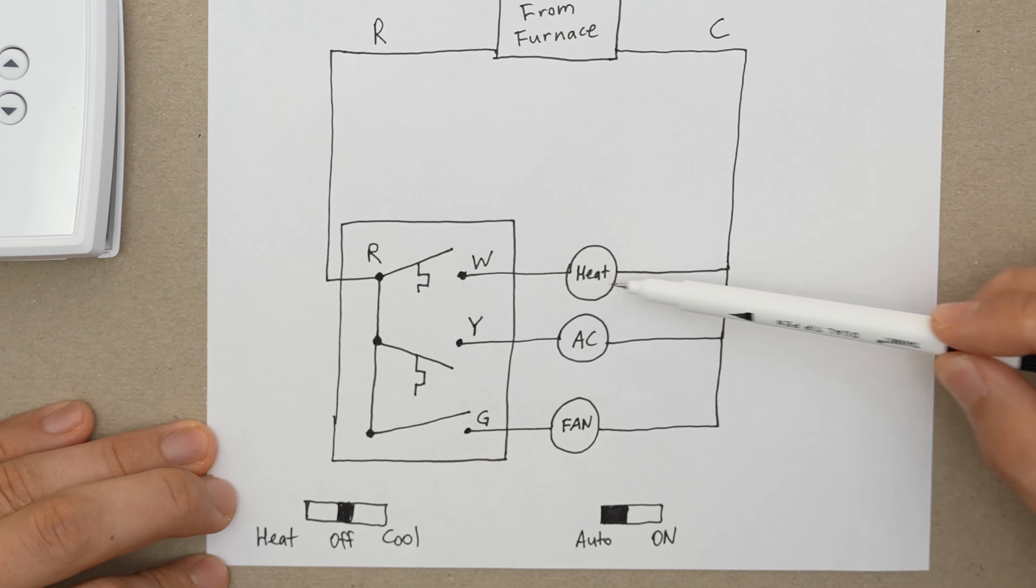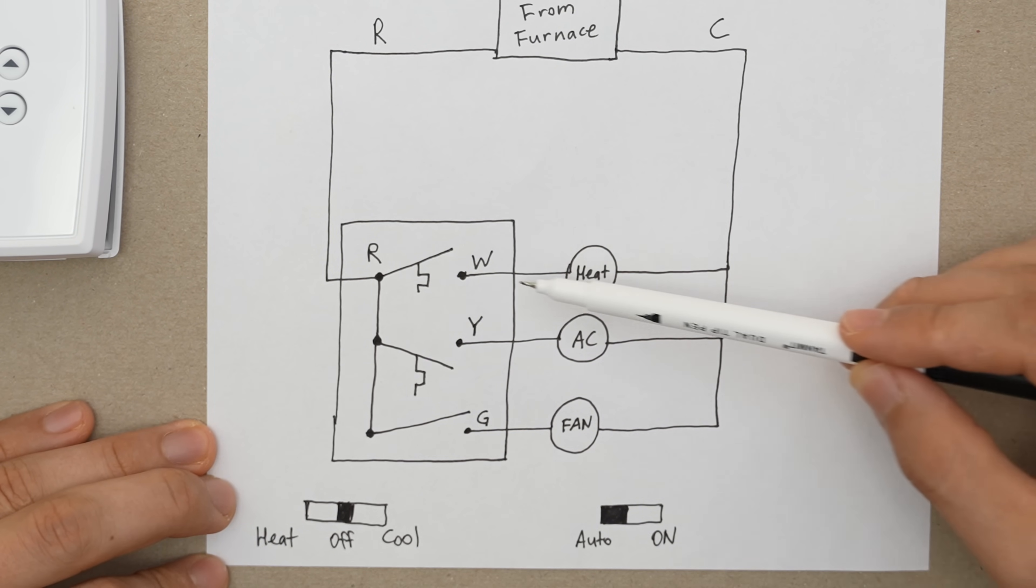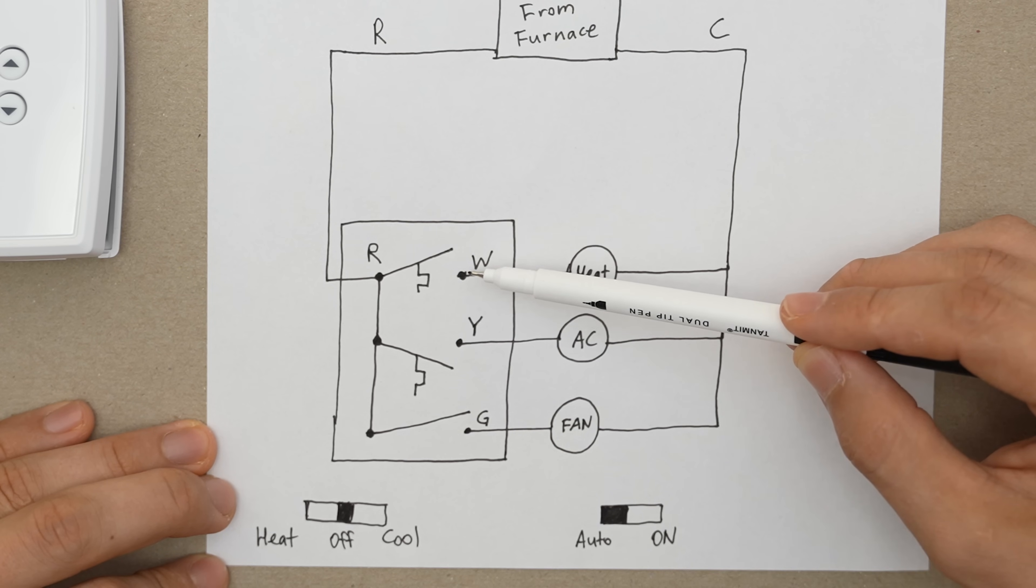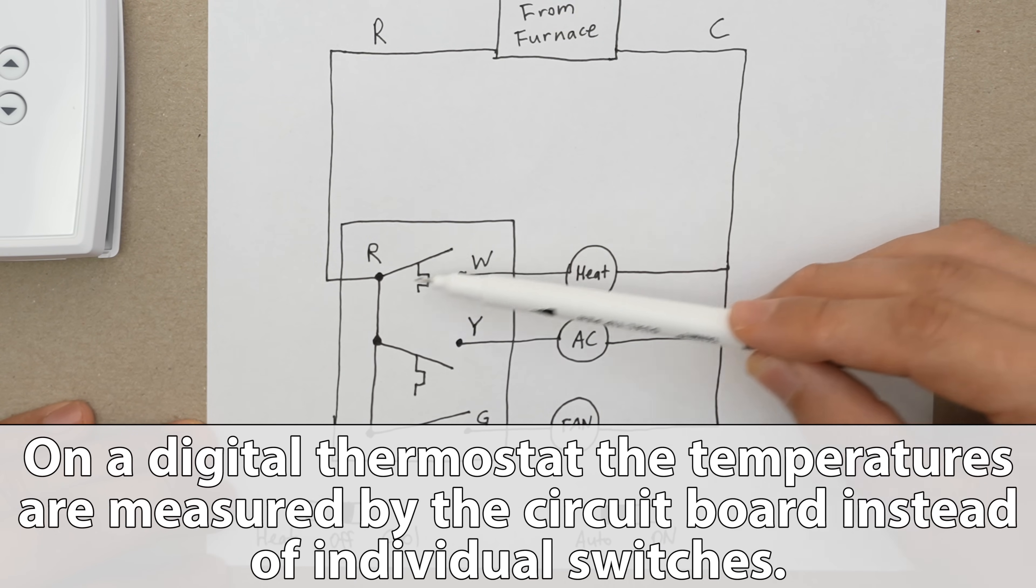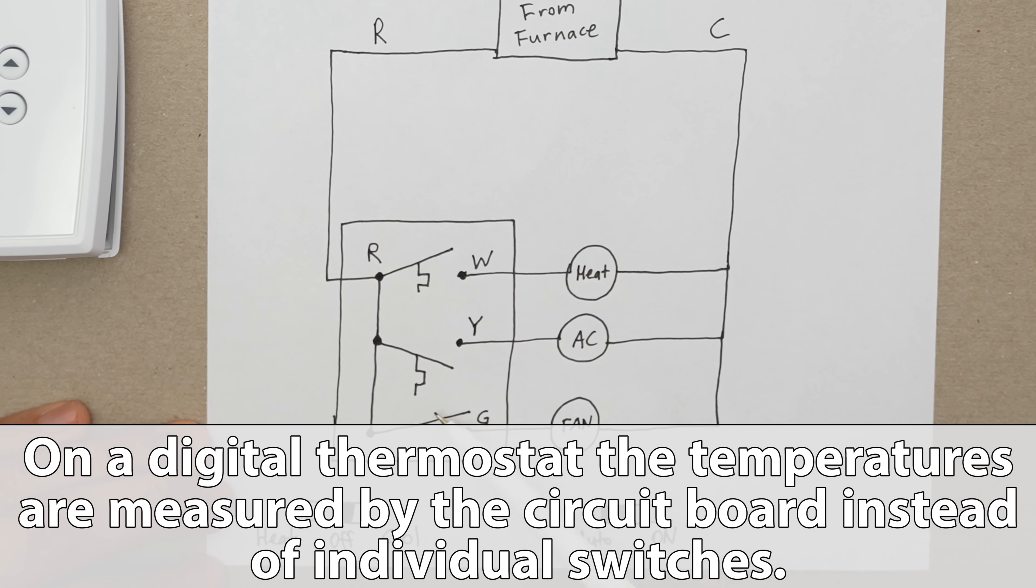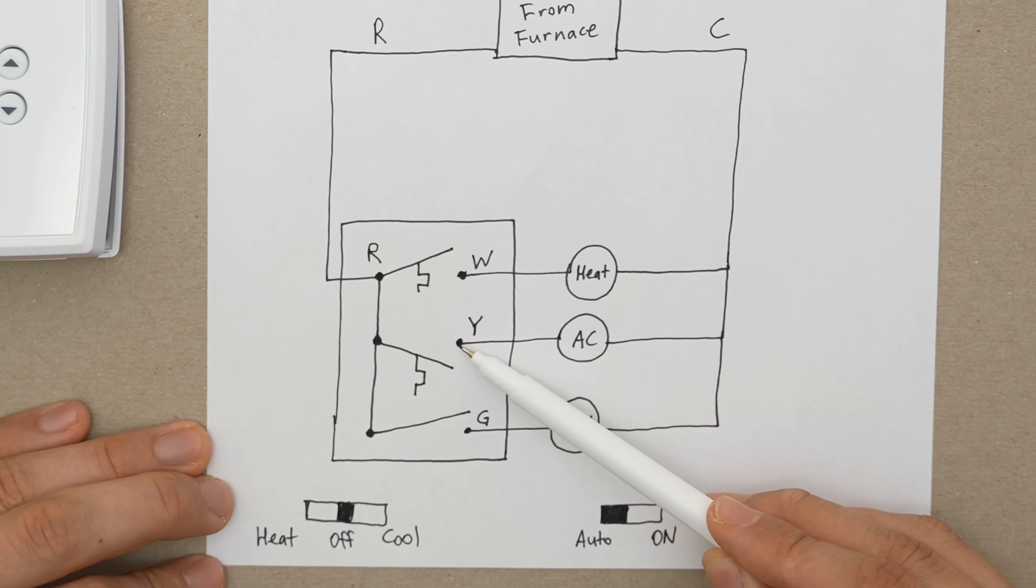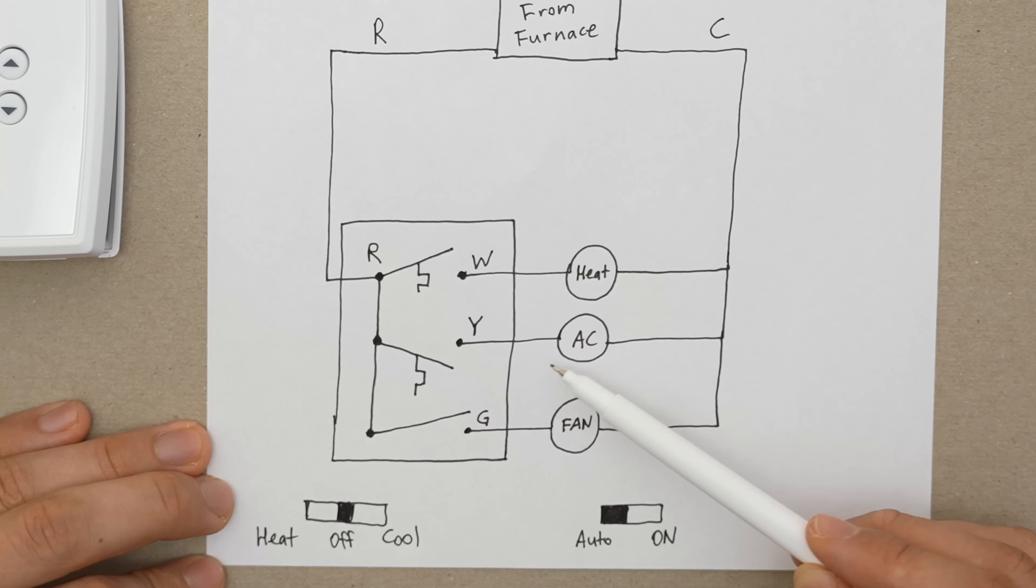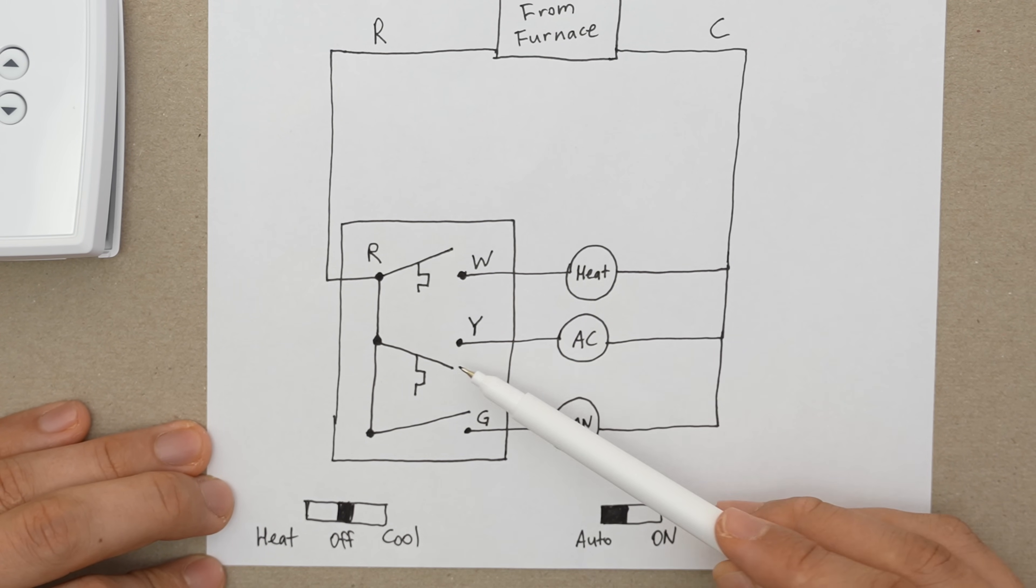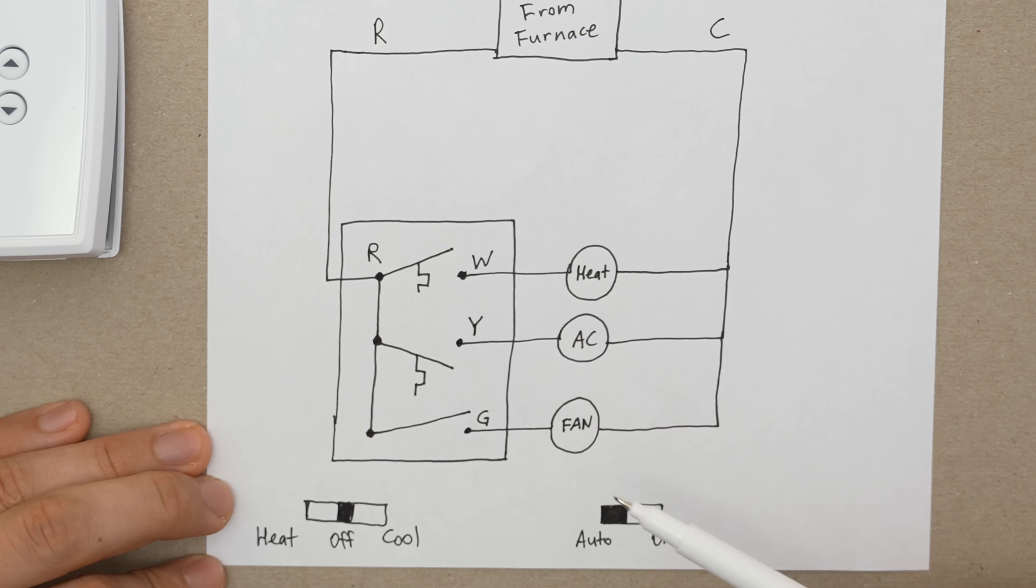This switch will lower until it touches this contact and boom, this W line gets energized and that turns on your furnace. Once the temperature in the house heats up, then this switch goes back up and interrupts the power. And the switch for the air conditioner works the same way. When the temperature inside of the house goes up, this switch goes down until it touches this contact and energizes the air conditioner. The air conditioner runs until it cools off the house, and this switch opens back up and interrupts the power, turning the AC off.